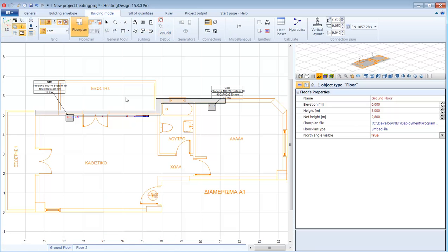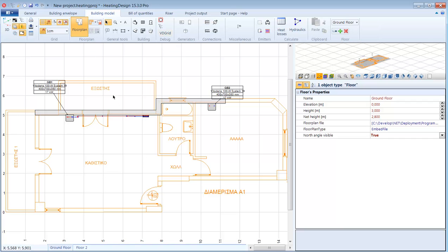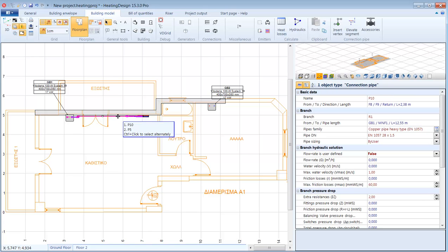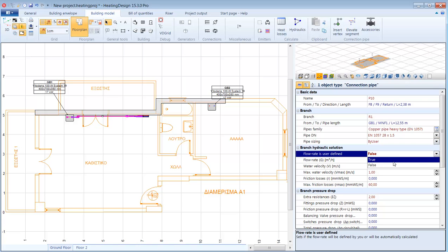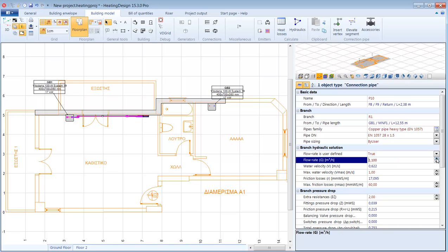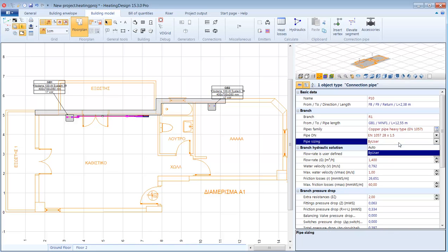If I change the flow rate calculation mode to manual then I can input my own value and see what happens to the pipe's other calculated properties, for example the water velocity and the friction losses. If I keep incrementing the flow rate then at some point the pipe's diameter will be changed to fit the new requirements.